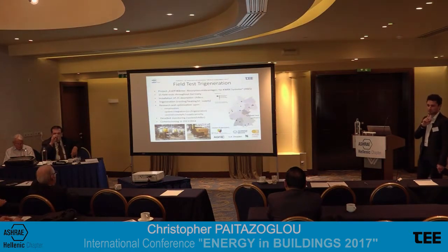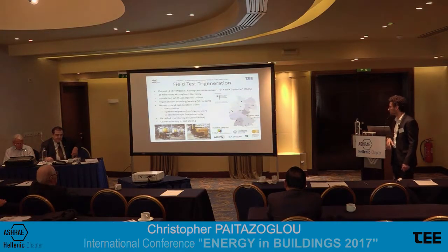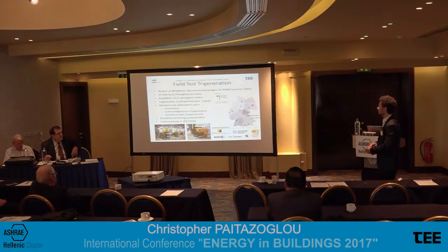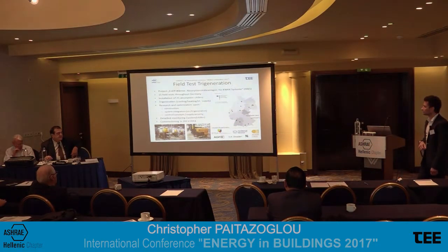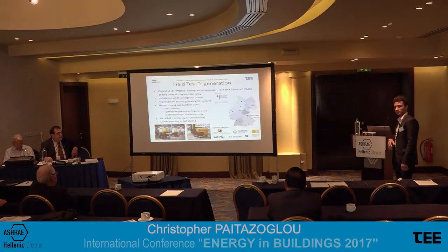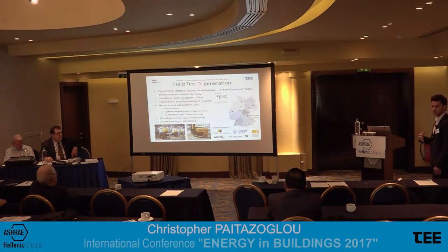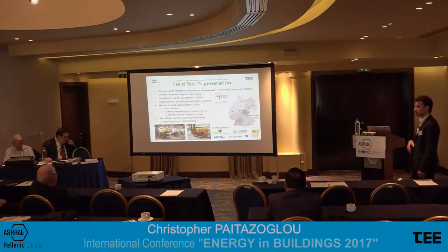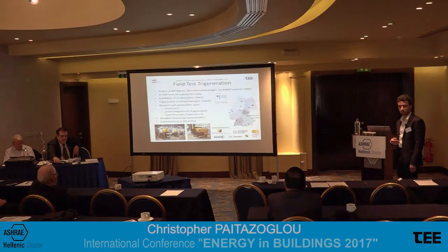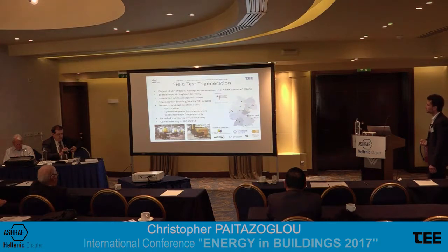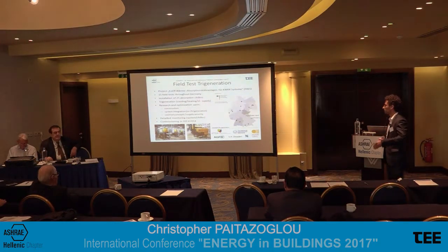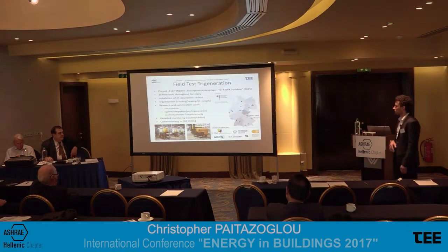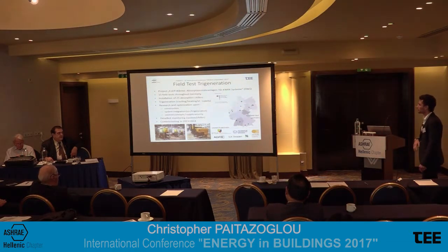So, field test trigeneration is the bigger project that we have in Germany. This has a very German title, which we abbreviate with FATS. It deals with 15 field tests throughout Germany, as you can see. In total, there are 25 absorption chillers installed. And the aspect of trigeneration is always there, because sometimes we have cooling, heating, and electricity supply. We are doing research and optimization in the fields of construction of the chillers, system integration, and last of all, and most important, the control concepts, not only for the chiller, but also for the interaction with the system. And also about the topics of supply security, because it's a very important issue here.